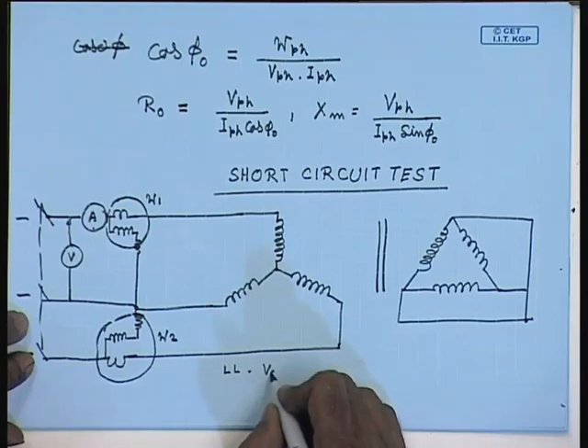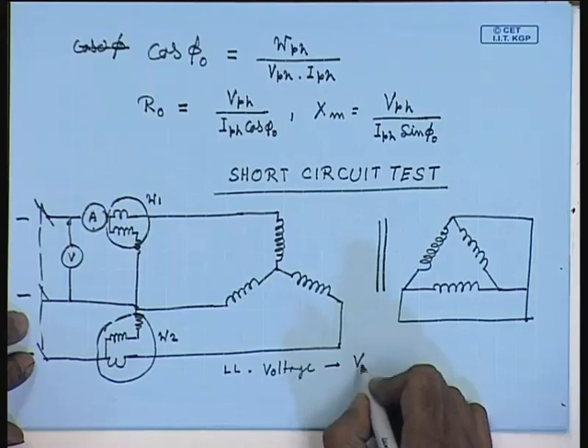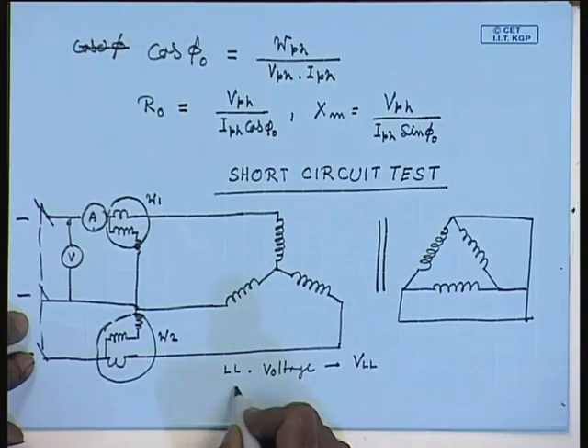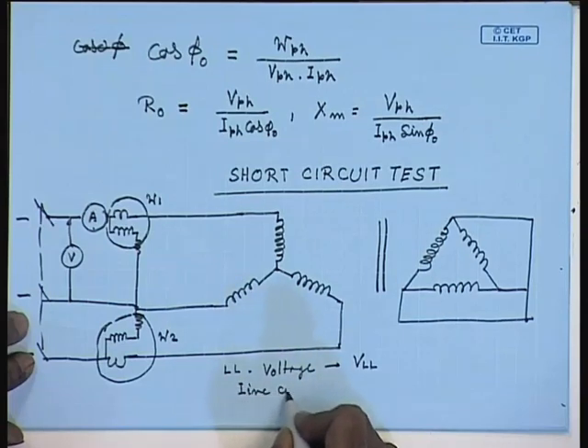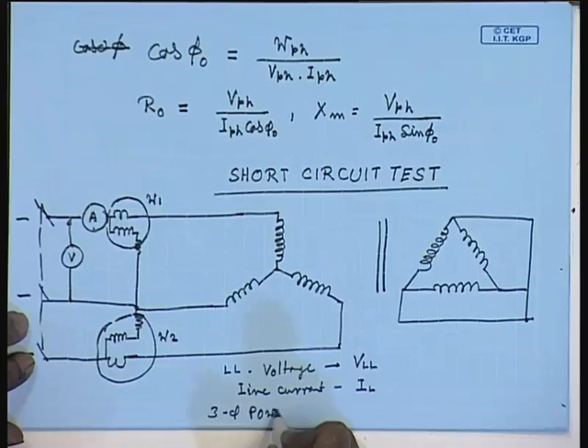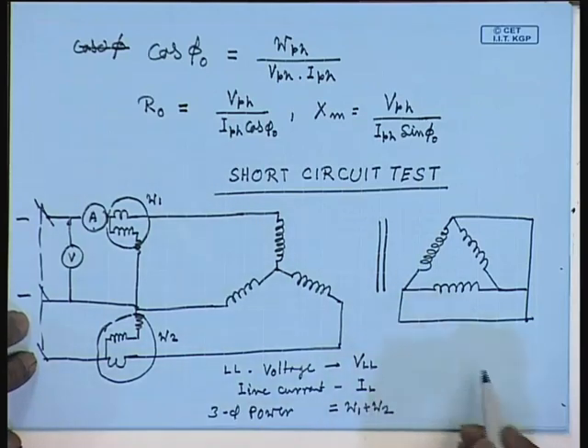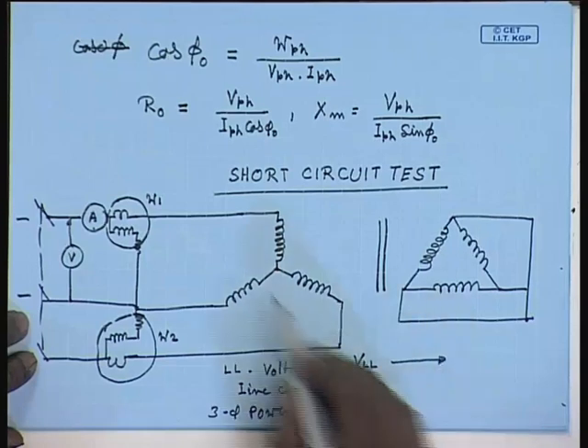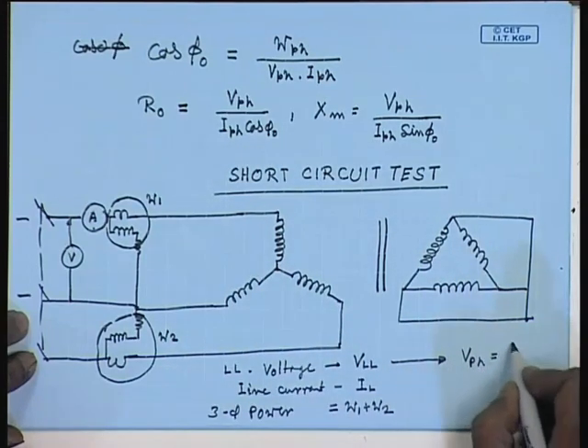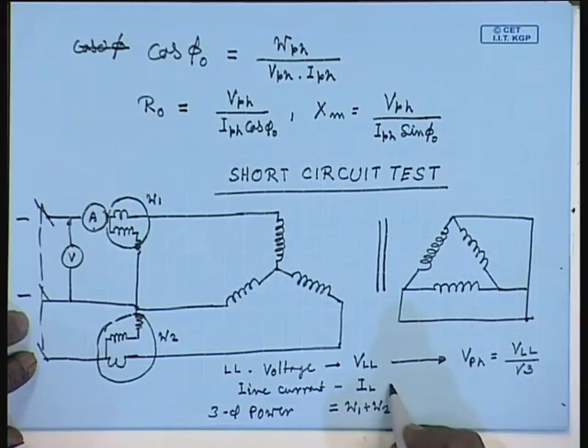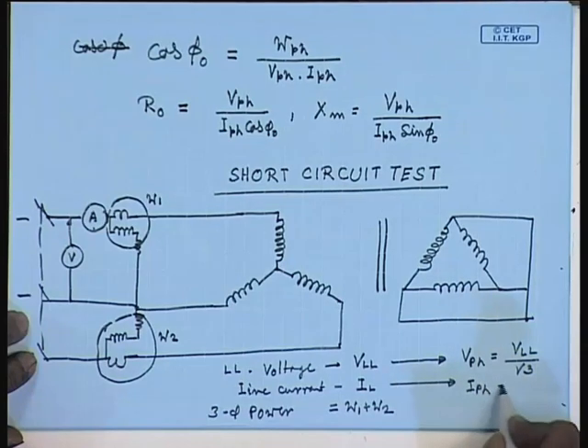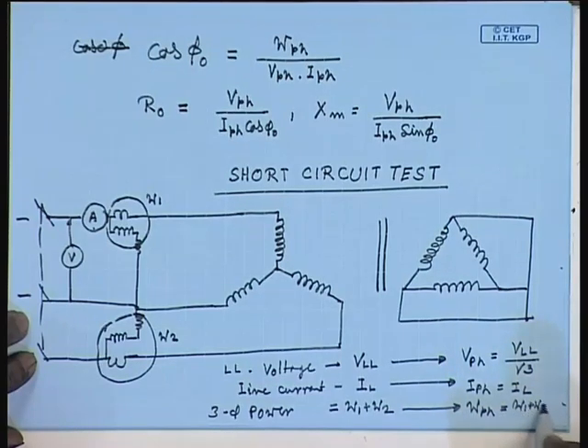then we will measure line to line voltage, which should be VLL, the line current IL, and 3-phase power equal to W1 plus W2. These we will convert to phase values again. So, this is star connected. V phase will be equal to VLL by root 3. Star connected, therefore, I phase is same as I line, and per phase power W phase equal to W1 plus W2 by 3.